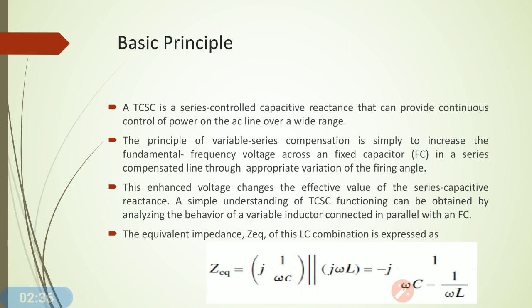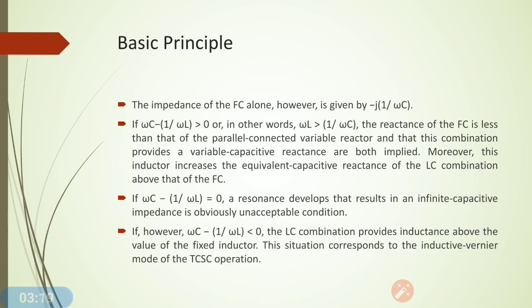Before the TCSC, we use a series capacitor in the transmission line to compensate the series inductive reactance. In order to control the reactance of the capacitor, we connect this capacitor in shunt with a Thyristor Controlled Reactor. The equivalent impedance of this LC combination is Z equivalent, equal to j(1/ωC) in parallel with j(ωL). The impedance of the capacitor alone is given by minus j(1/ωC).